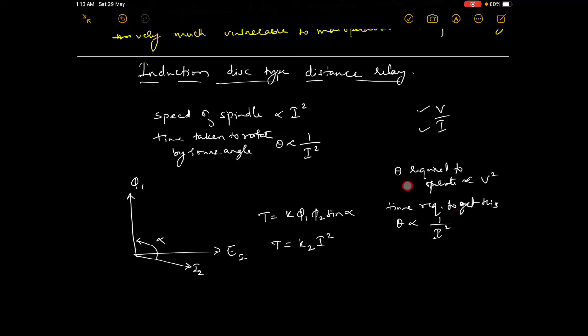Now this theta required is operating based on the voltage. So less the voltage, less the restraining force. The voltage will be less when there is a fault. When there is a fault, less voltage, less restraining force. See, voltage is the restraining force. When that is less, it will make a contact. That will also decide the theta.